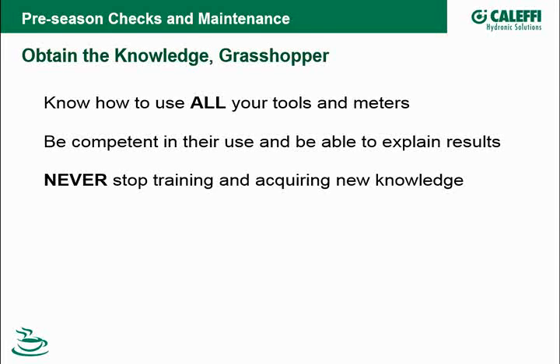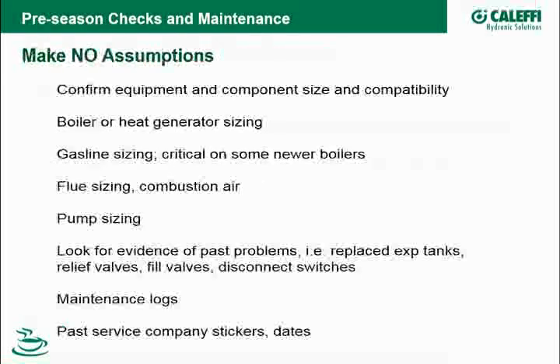If you walk into a house and it's a 15,000 square foot house and you see 3 boilers there at 1 million BTUs or something like that, there could be that somebody's oversized the equipment or undersized it. So in some cases it's wise to do a heat load calculation on the building just to prove to the owner, well, you've made upgrades to this home over the years and now your heat load's reduced, so it's time to maybe look at sizing down this equipment.